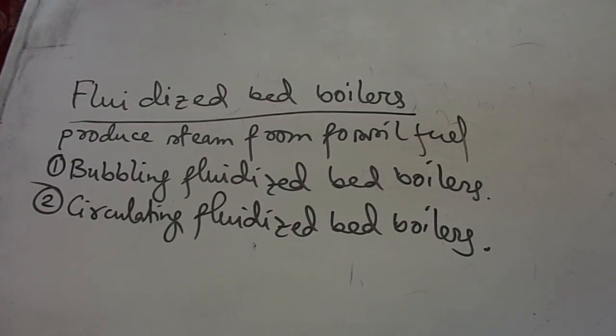Whereas the CFB boiler, the circulating fluidized bed boiler, is said to be the second generation fluidized bed boiler. There are two sections. First section is the furnace of a fast fluidized bed, and the second one is the gas solid separator. Coal is generally injected into the lower section of the furnace. It is sometimes fed into the loop seal, from which it enters the furnace along with return hot solids. The primary combustion air enters the furnace through an air distributor or grate at the furnace floor. The bed temperature is nearly uniform in the range of 800 to 900 degrees centigrade.